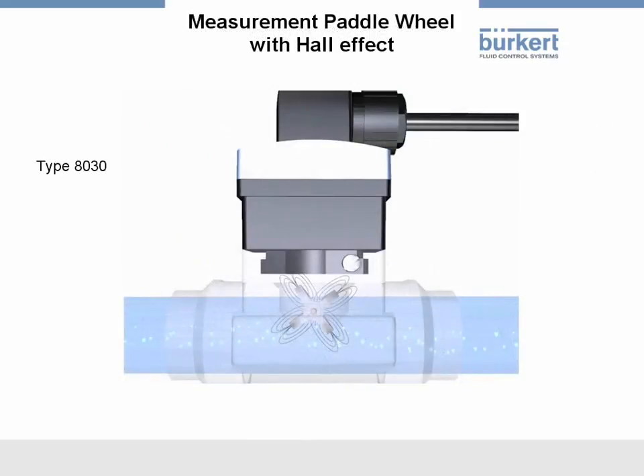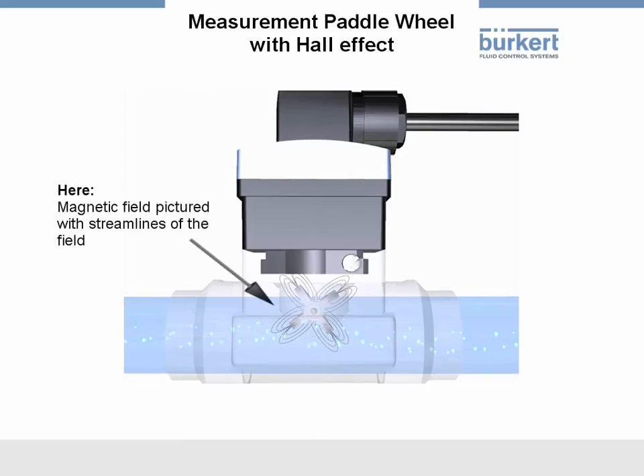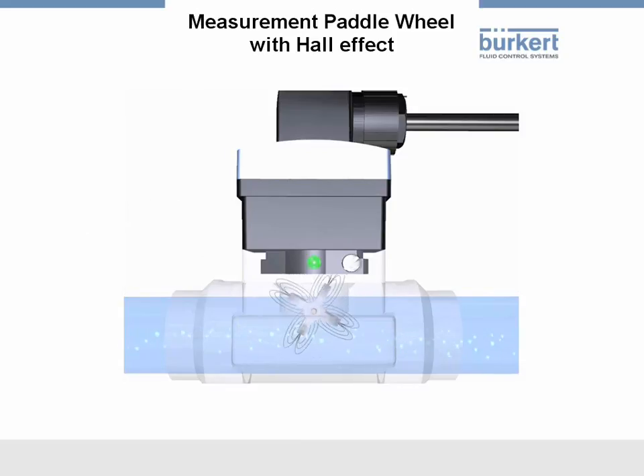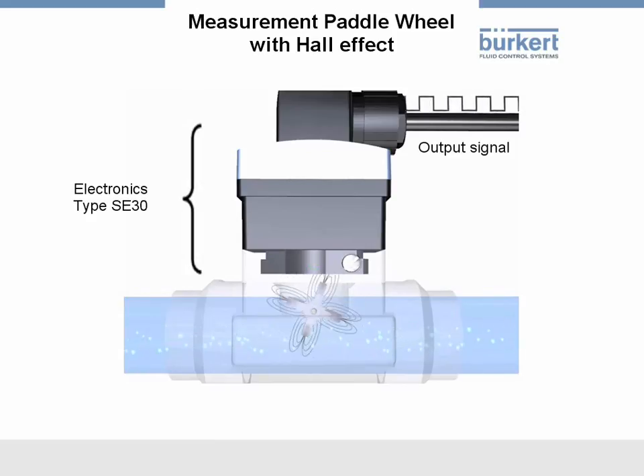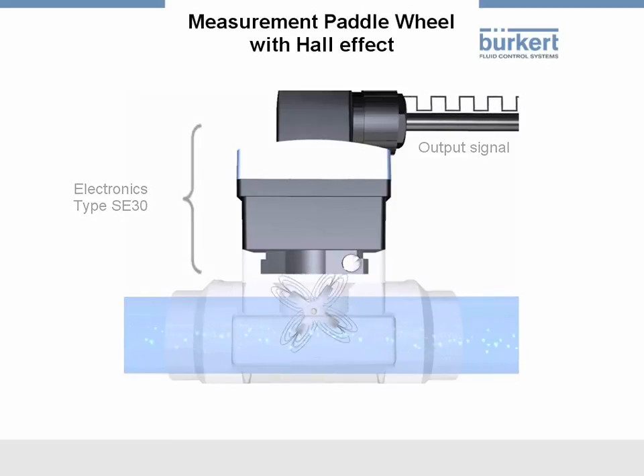If using a Hall effect sensor, the paddle wheel is made of plastic, for example, PVDF or PP. A permanent magnet is cast into each of the four paddles. The paddle wheel rotates on the wear-resistant ceramic spindle, and a Hall effect sensor detects the magnetic field of the rotating paddle wheel. For each 360-degree rotation of the paddle wheel, four signals are generated. The electronic circuit converts the signal to a rectangular frequency. The customer can define how many pulses are output for each volume unit, per liter, for example.